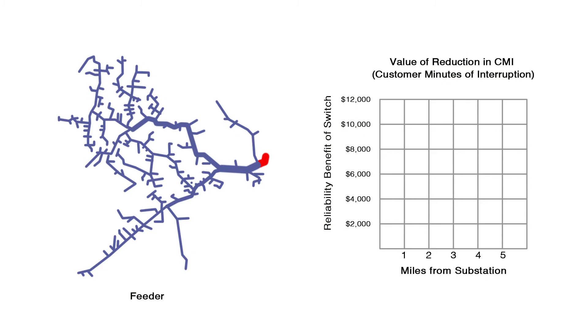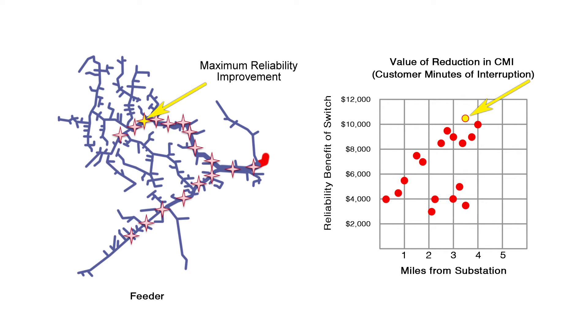As a first step, we simulate the placement of a switch at every single location on that circuit or feeder, and we calculate the new predictive reliability statistics and compare the difference. Through that iterative process, we pick the location that has the maximum reliability improvement and propose the siting of the switch at that location.